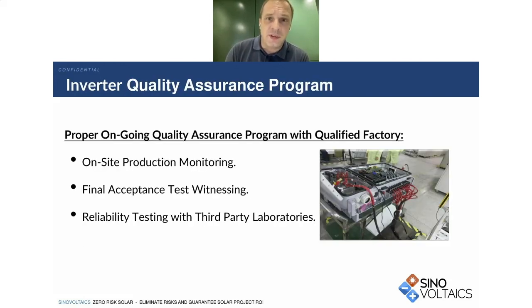Aside from proper qualification of the inverter supplier and the specific workshop producing your inverters, once a supplier has been audited and selected, proper quality risk management should also involve an ongoing quality assurance program on site to identify and correct issues early, before an inverter is shipped to the project site. Such scope includes predominantly on-site production monitoring and final test witnessing.